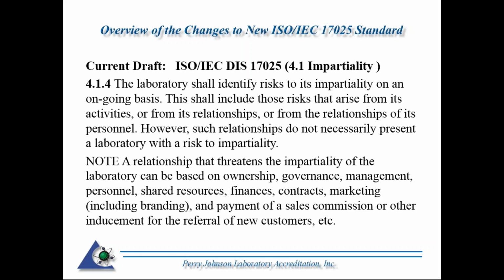And the current draft, under 4.1.4, the laboratory shall identify risk, and this is a key word. This comes up a lot in the new standard: identifying risk to its impartiality on an ongoing basis. This shall include those risks that arise from its activities or from its relationships, or from the relationships of its personnel. However, such relationships do not necessarily present a laboratory with a risk to impartiality.